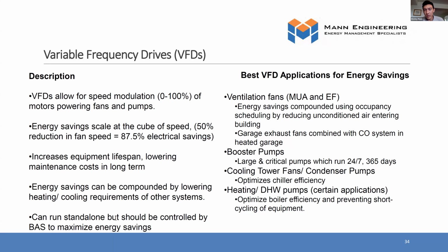Now, garage exhausts is another example where if you have a CO system for your garage exhaust fan, if the garage is heated too, that can provide additional savings. Now you can modulate the fan speed of the garage exhaust system to match the actual requirements based on the CO. Booster pumps, another great example. That's a pumping system that's running 24/7, 365. So any reduction in speed there will provide great savings in the long run.